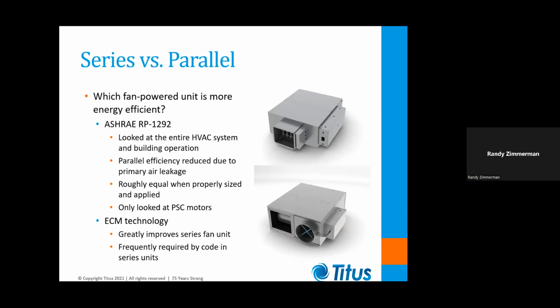ASHRAE won't publish because it was not done under their auspices, but it is available through places like AHRI because all of the research was donated to industry. And I've got a copy of the report also. And basically it showed that when you went to the newer ECM motors, they greatly improved the efficiency of the series unit because the series unit could take more advantage of the high efficiency of the ECM. And so as far as I'm concerned, the ECM is now the state of the art. Excuse me, I should say the series unit with ECM is the state of the art.